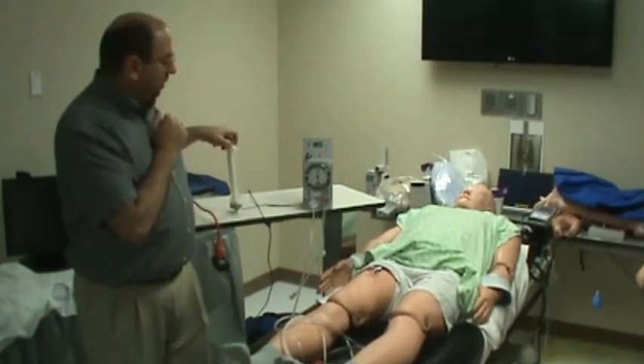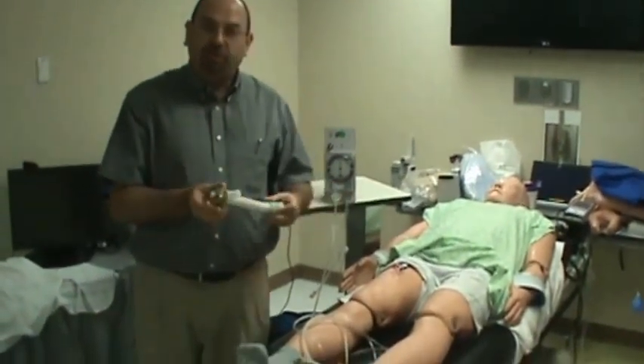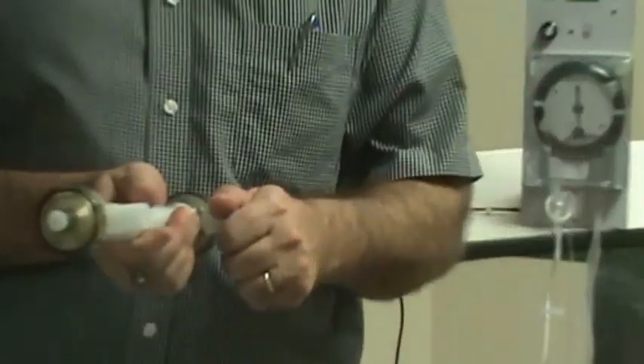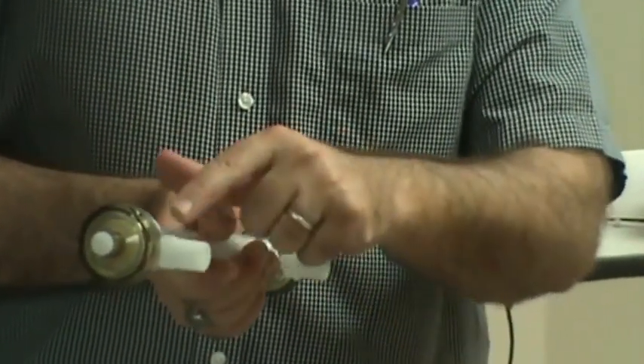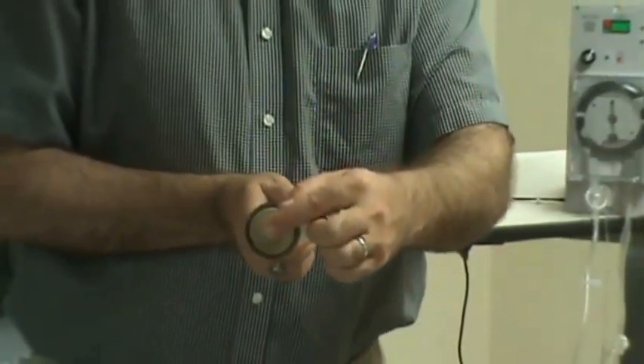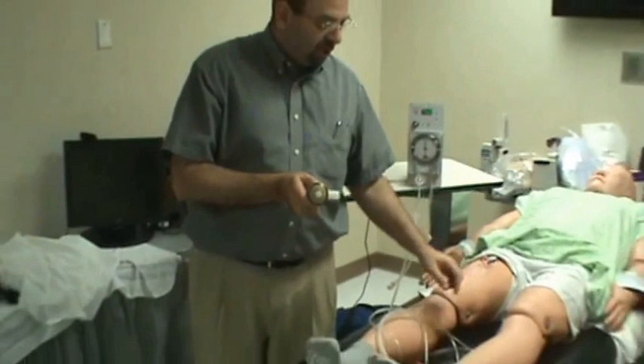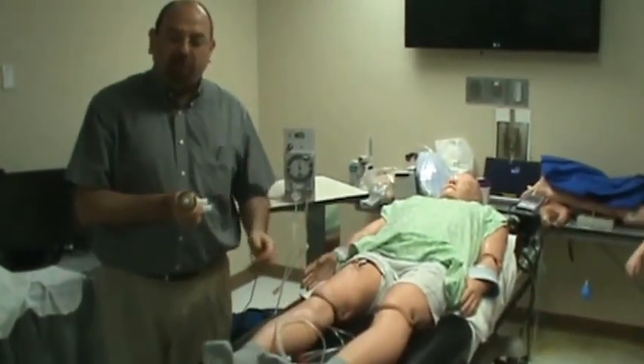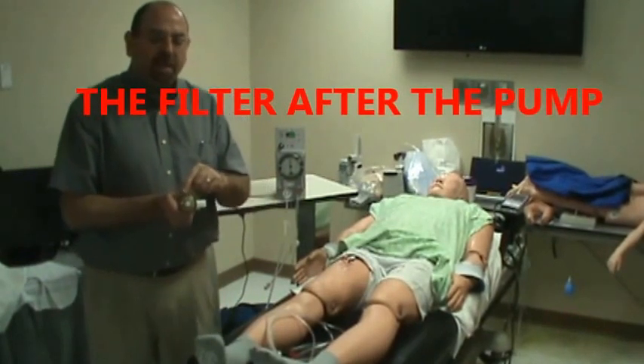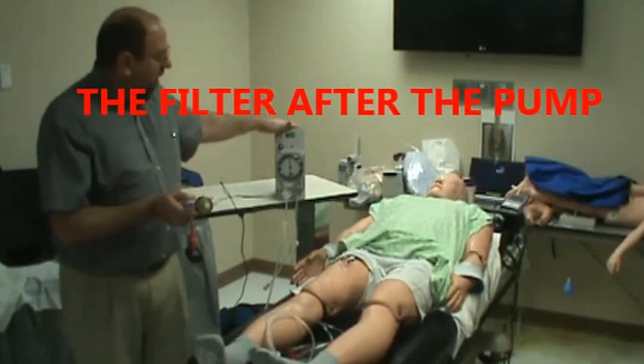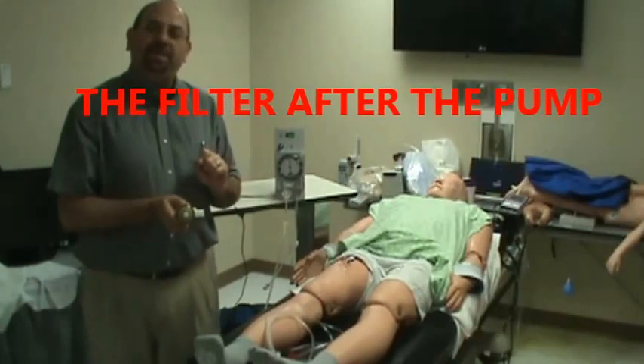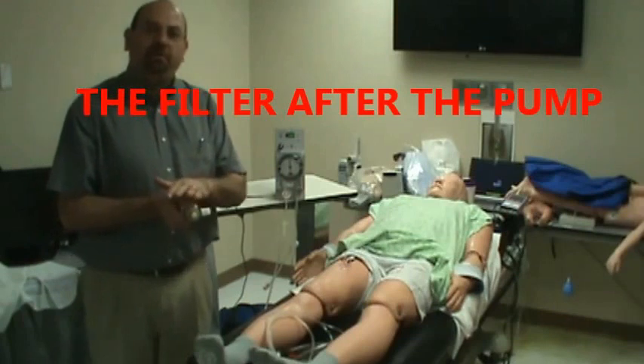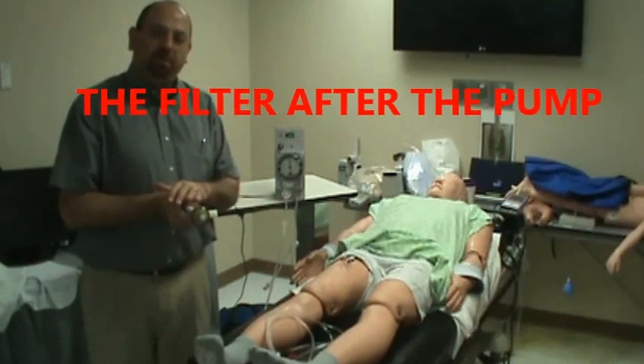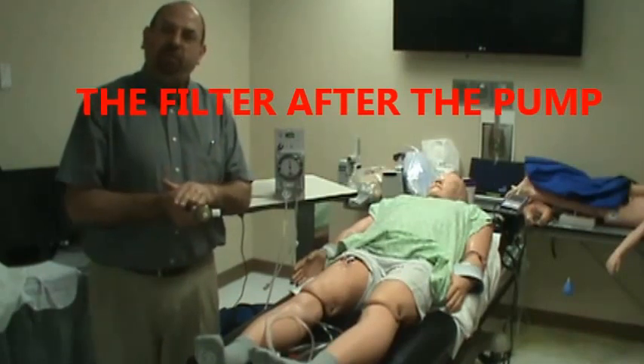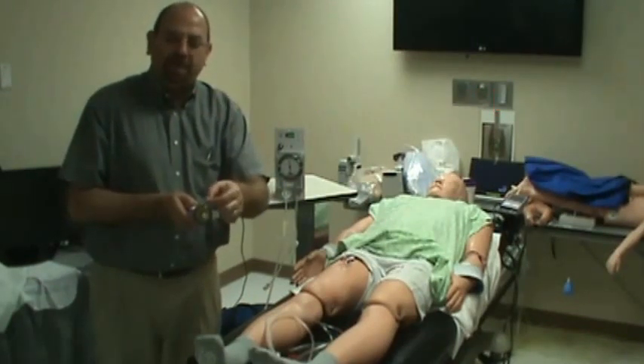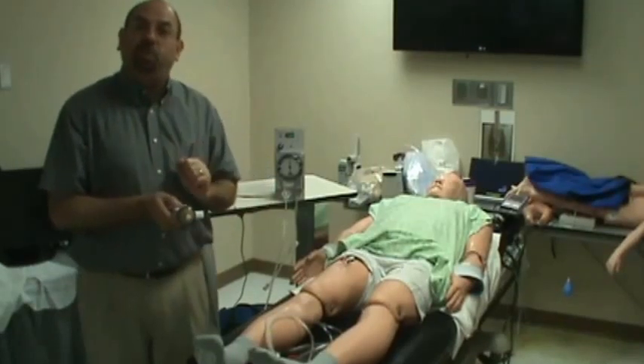And then you need a simple filter that you utilize for ultrafiltration, where you keep one end capped and tight, and filtration is going to come out of the other end. And then you connect the other side of the filter back to the patient using the same type of tubings. Now keep in mind, the filter has to be after the pump. Here's the pump. The filter has to connect after the pump. The reason is that you have to create a positive hydrostatic pressure within the filaments and the hollow fibers of the filter, because if you place the pump beyond the filter, it is suction and it creates negative pressure, and ultrafiltration would be very limited.